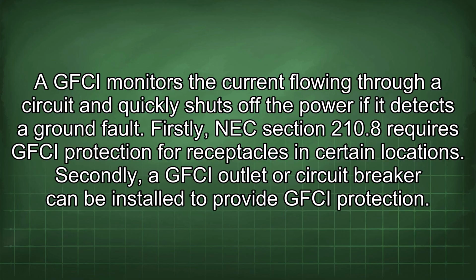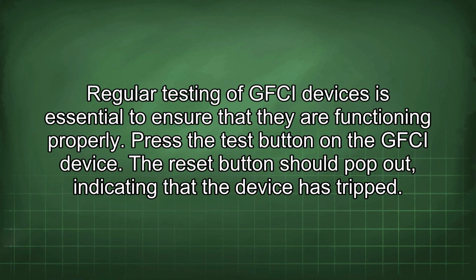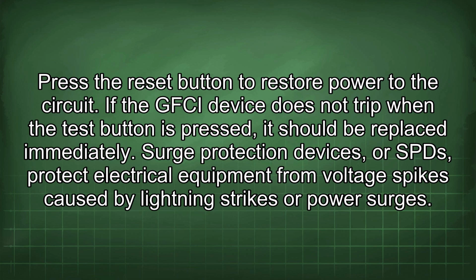Secondly, a GFCI outlet or circuit breaker can be installed to provide GFCI protection. Regular testing of GFCI devices is essential to ensure that they are functioning properly. Press the test button on the GFCI device. The reset button should pop out, indicating that the device has tripped. Press the reset button to restore power to the circuit. If the GFCI device does not trip when the test button is pressed, it should be replaced immediately.